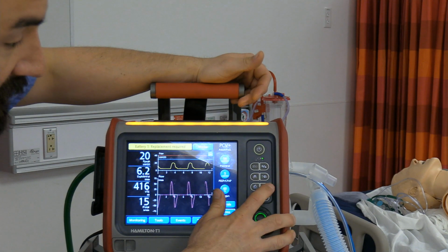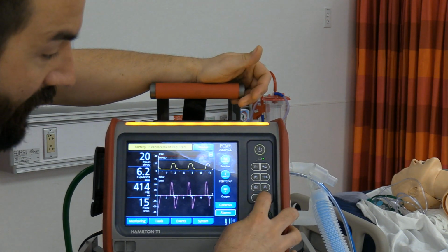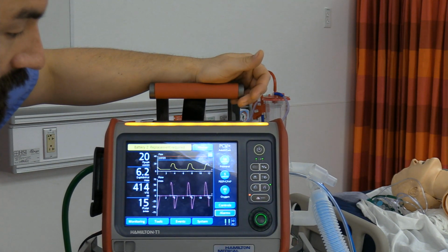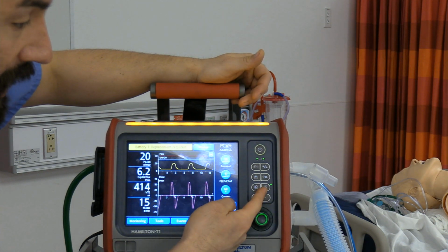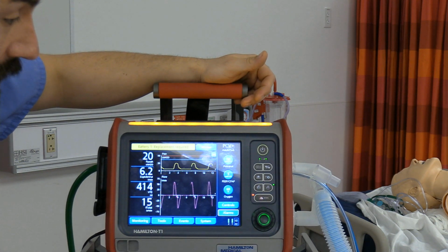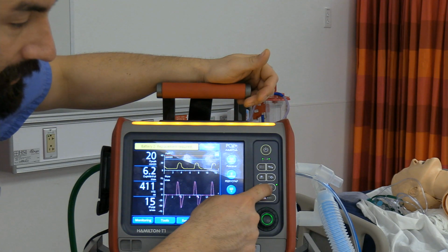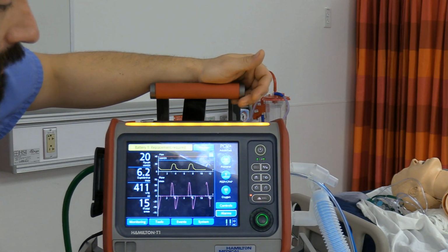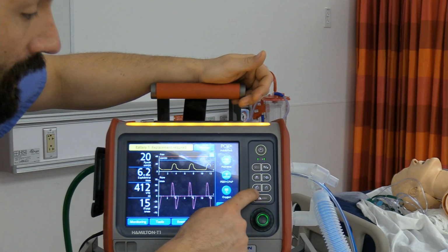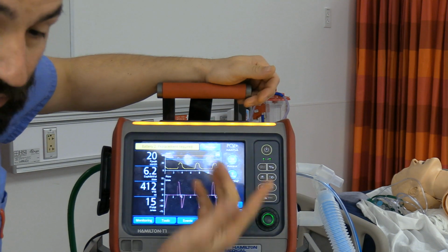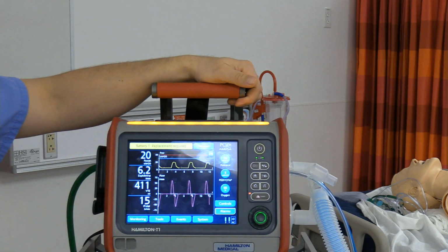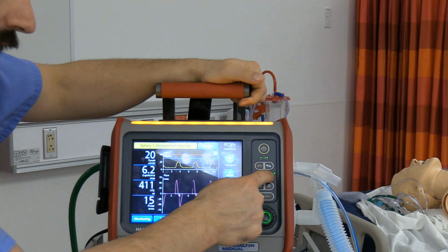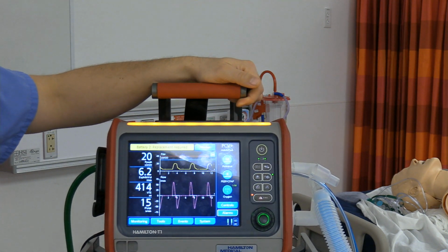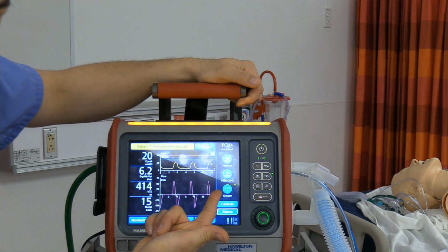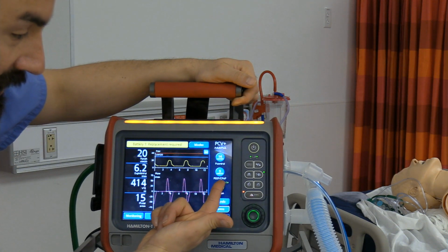So a couple other things. If I was running the neb feature, I could hit this button, and it's going to give that nebulizer on inspiration, which is ideal. Using a vibrating mesh neb would even be better. We have 100% O2, so if my patient was desaturated, I'm getting ready to suction them, and I wanted to hyperoxygenate, I can hit 100% O2, and it's going to bump them up for 2 minutes, and it'll show you green, we're at the 100%, and it's got a countdown.